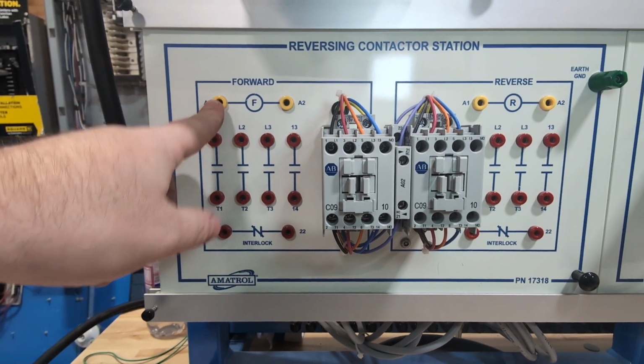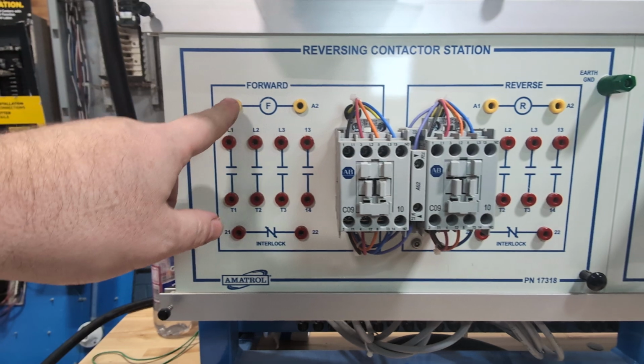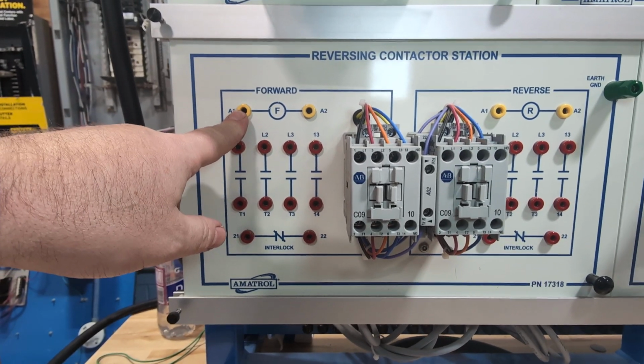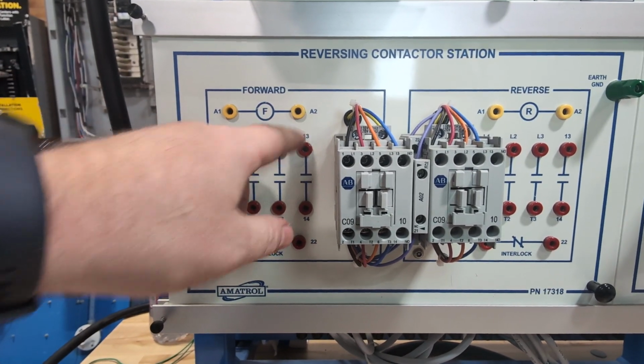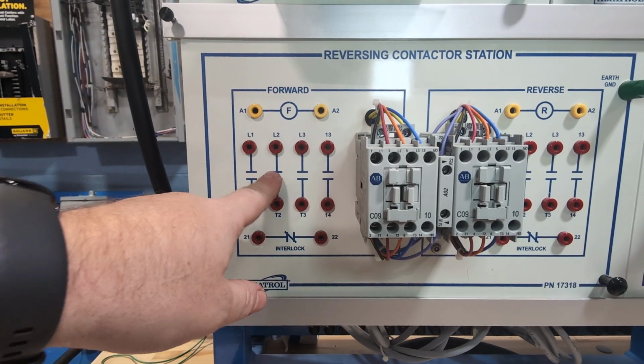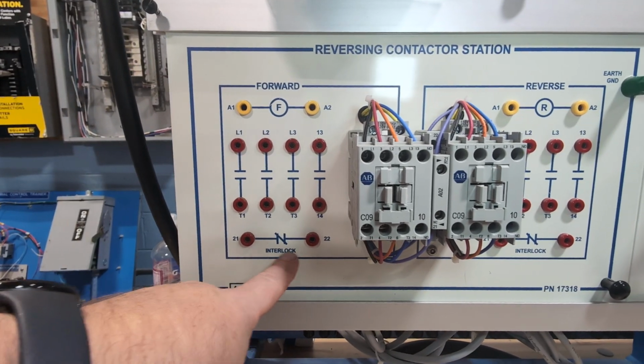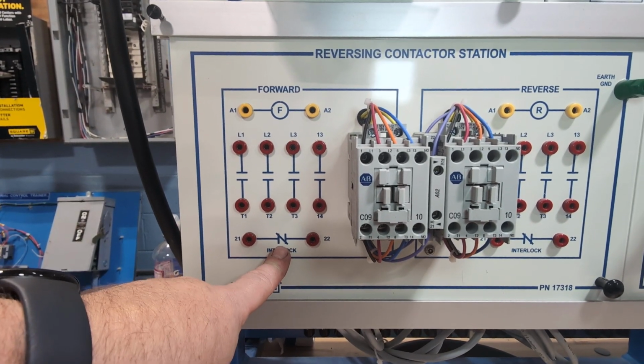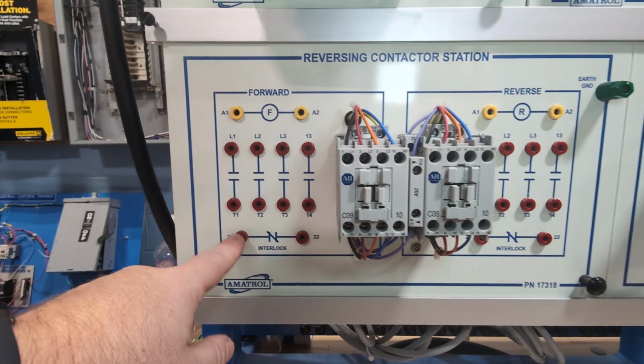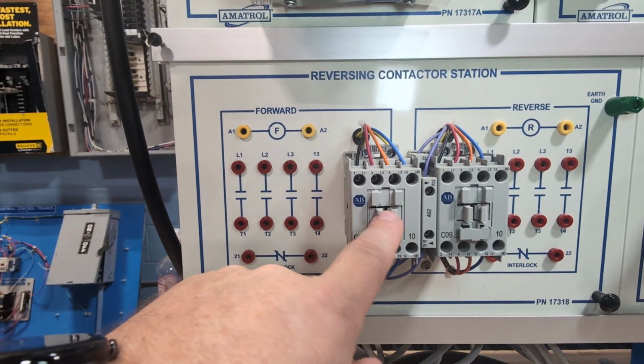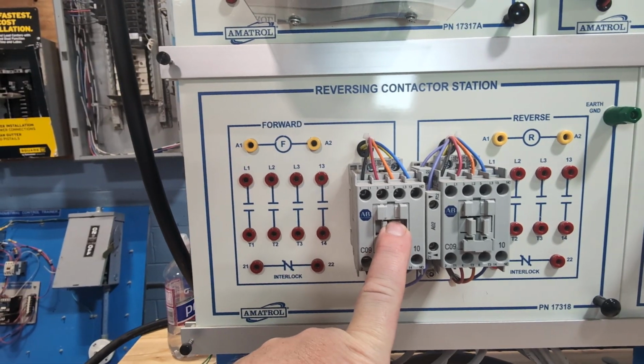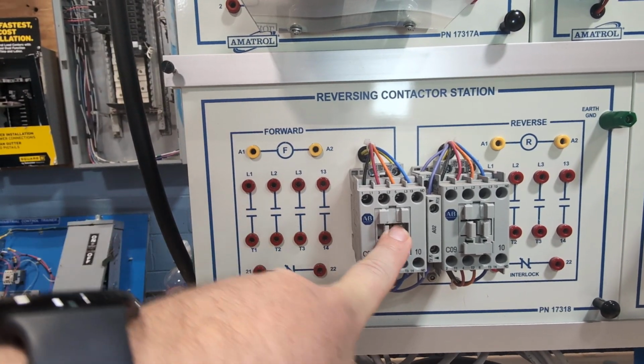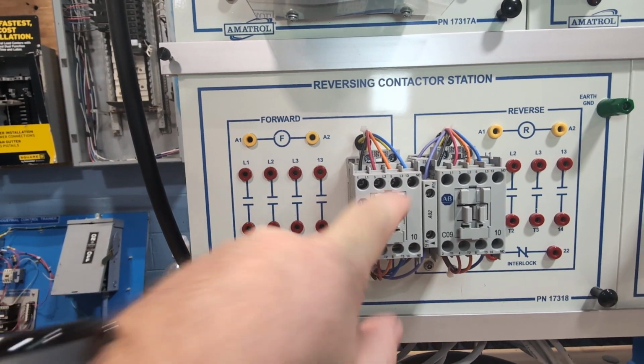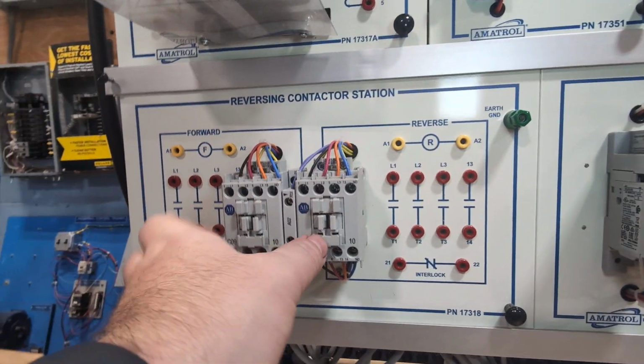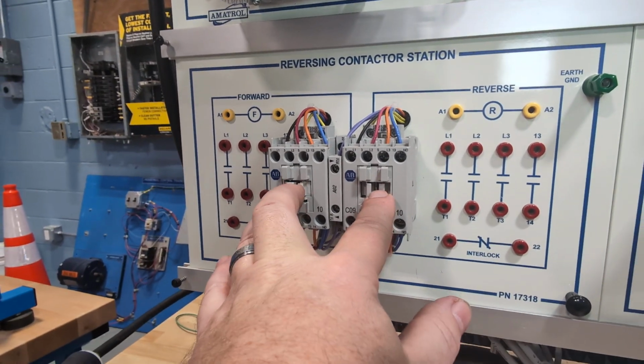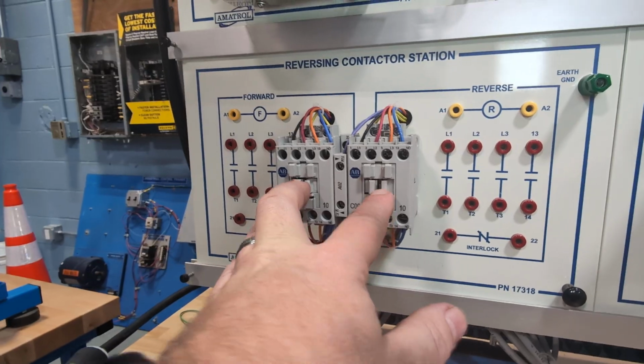So the coil is hot with either 120 volts and then neutral, or 24 volts common, positive, and then 24 volts negative. Here's my switches, normally opens. With the interlock here, normally closed. Okay? This indicates when I'm pulled in, my motor's running. If you use that or that, depends on what you want to use. Okay? Now reverse is hit, same deal. I can't change state. It's engaged.